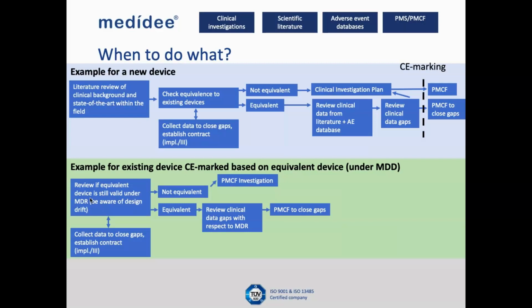And if you have any old devices that have been on the market for years and years, you should be very aware that your device has not drifted in design, which means that in iterative updates of the device, you may end up with a device that is not equivalent to the device that you originally claimed equivalence to. If you end up with the conclusion that your device cannot be claimed to be equivalent to the other device anymore, you need to do a PMCF investigation right away to close those gaps in order to be ready for the application of MDR. If you can still claim equivalence to the original device, you should do the same thing as for the new device.